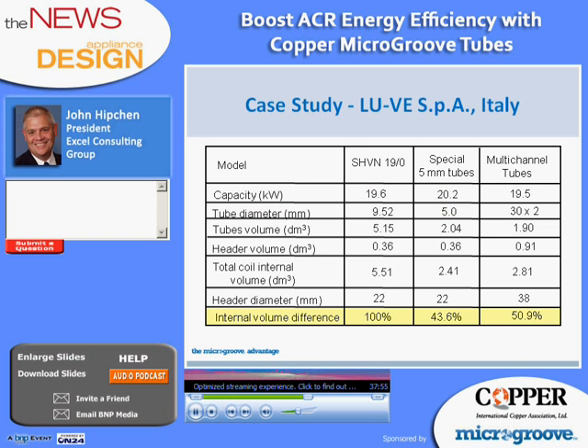And in this row, you can see that they were able to reduce the refrigerant charge in the aluminum tube design to about 51% of the refrigerant used in the existing design. But the 5mm copper tube design only used about 44% of the refrigerant compared to the original design. And that's a further reduction of refrigerant charge by another 16 or 17%.